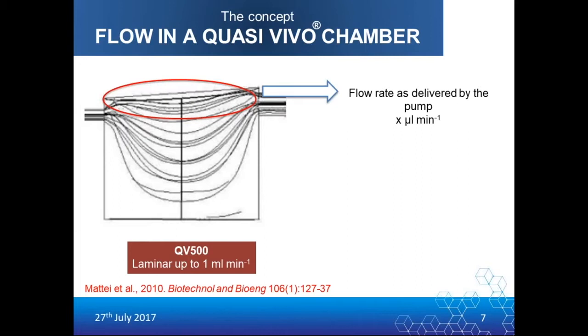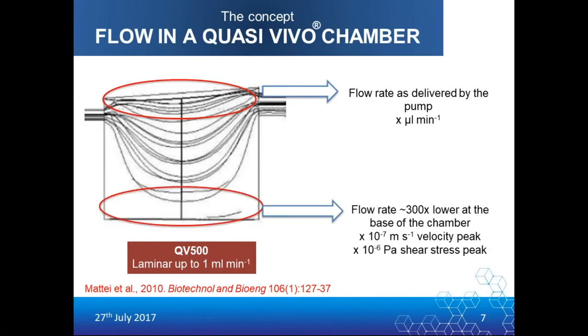Within the chamber, the flow is laminar up to pump speeds of 1 ml per minute. But if we look at the flow characteristics within the chamber, the flow rate as delivered by the pump is only seen at the very top of the chamber. As we move down the chamber towards the area at which the cells are cultured, the flow rate is around 300 times lower than it is at the top. And this means that we achieve physiologically relevant shear stress and velocity peak levels. You can read all about the development of our chamber in Mattei et al., and that's the paper quoted on this slide.